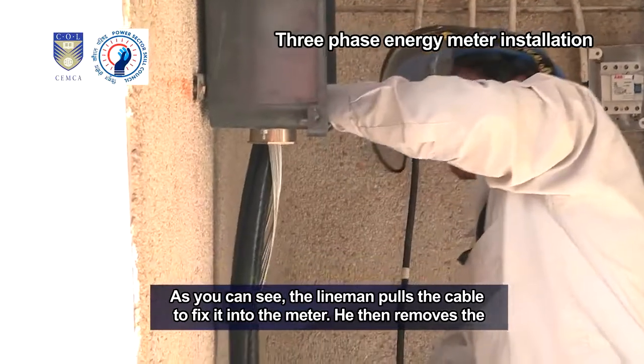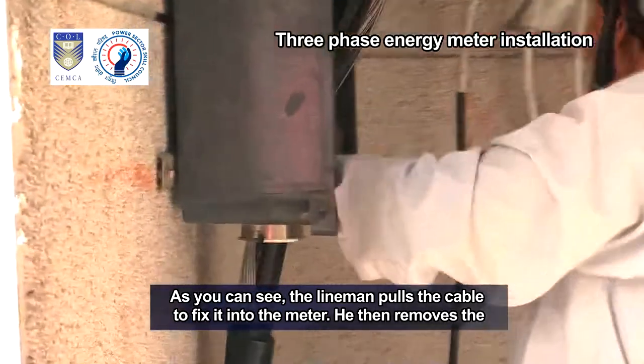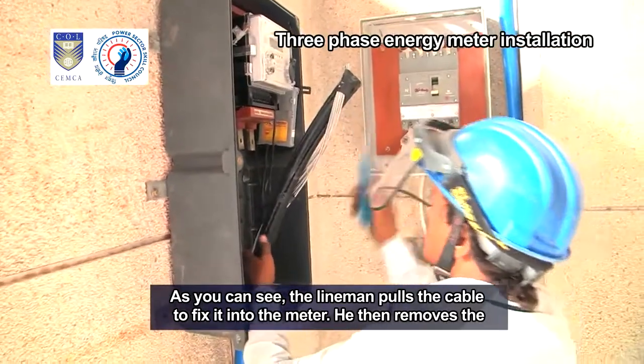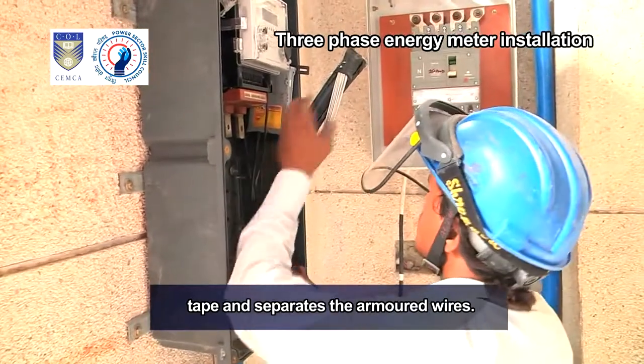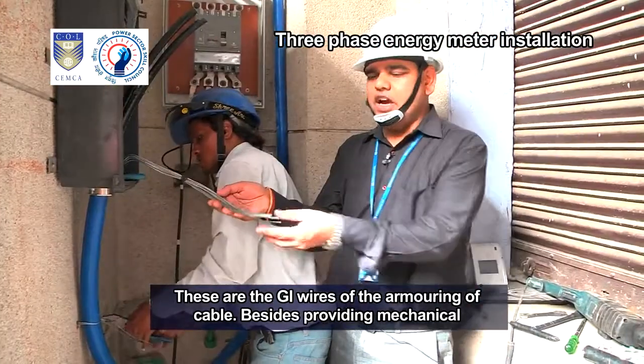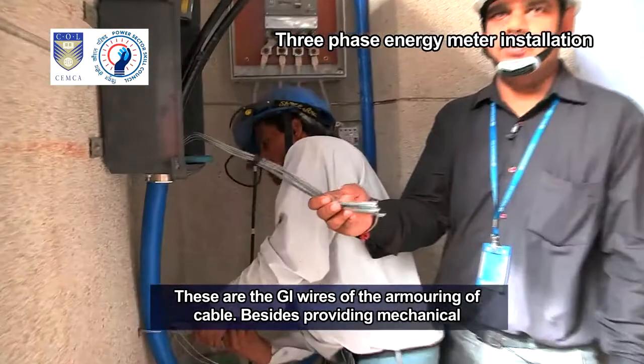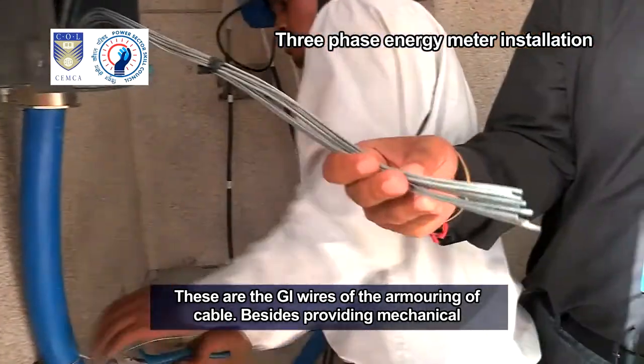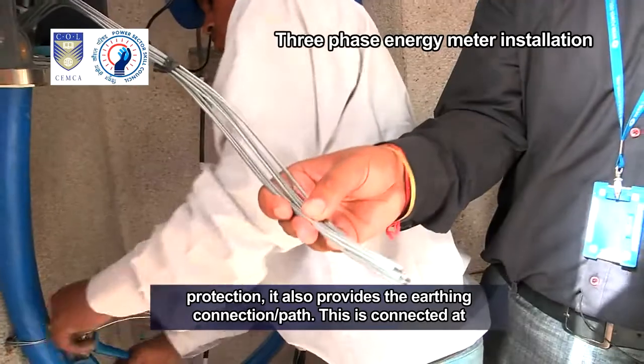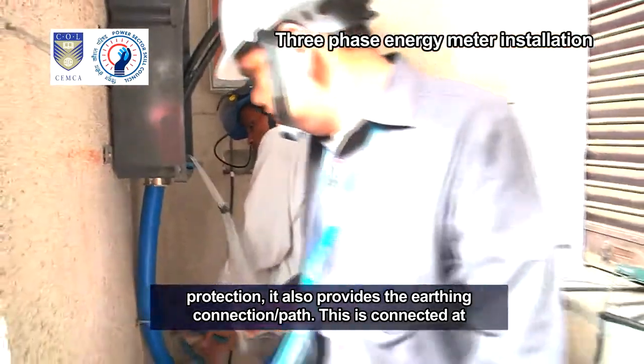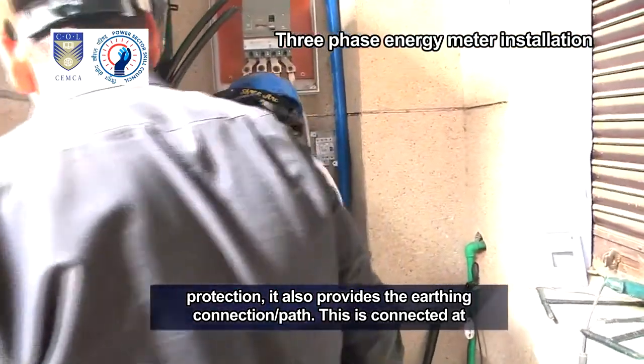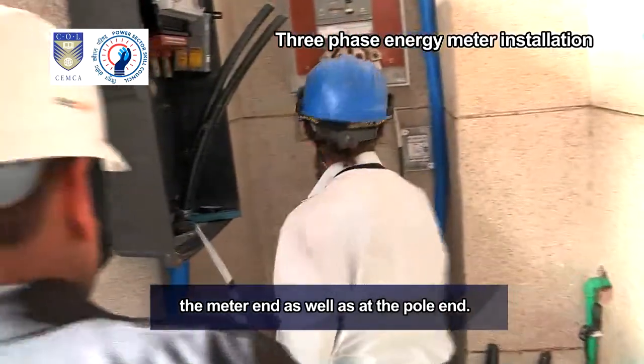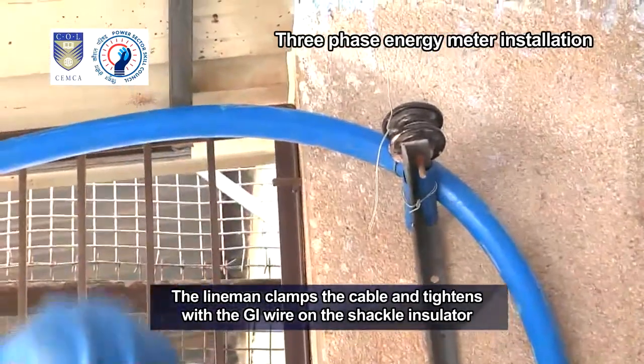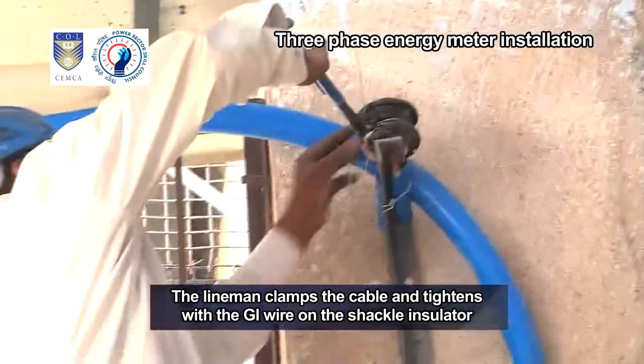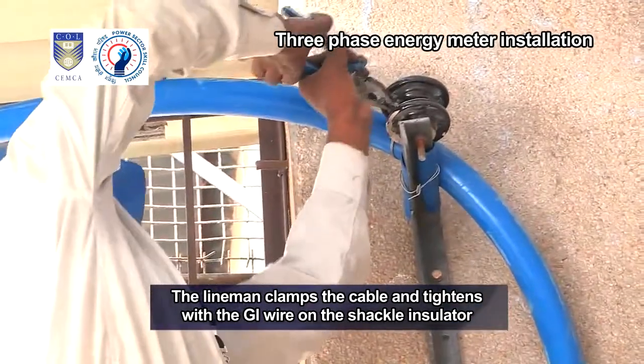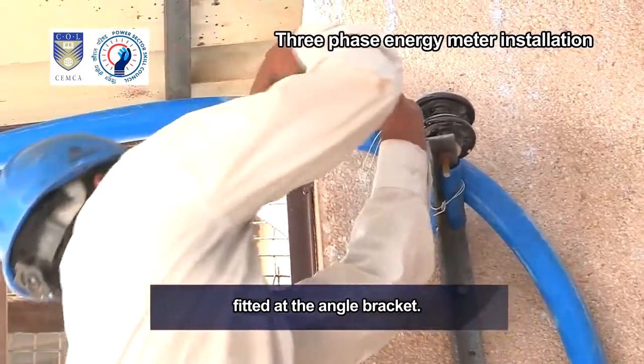As you can see, the lineman pulls the cable to fix it into the meter. He then removes the tape and separates the armored wires. These are the GI wires of the armoring of cable. Besides providing mechanical protection, it also provides the earthing connection or path. This is connected at the meter end as well as at the pole end. The lineman clamps the cable and tightens with the GI wire on the shackle insulator fitted at the angle bracket.